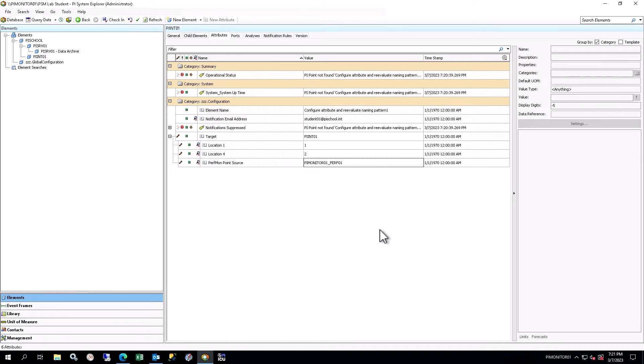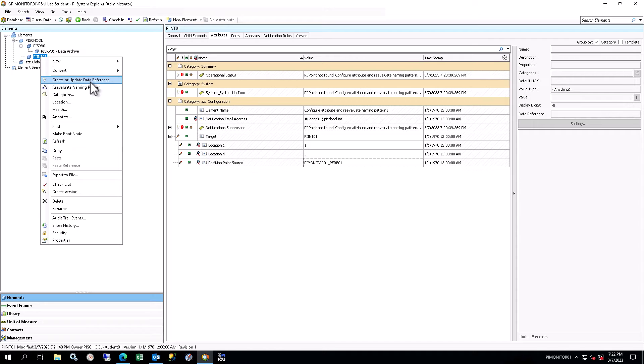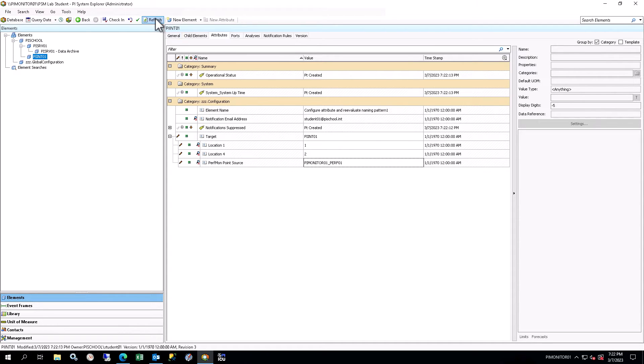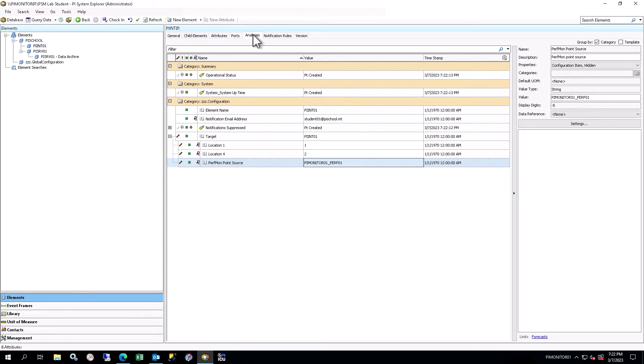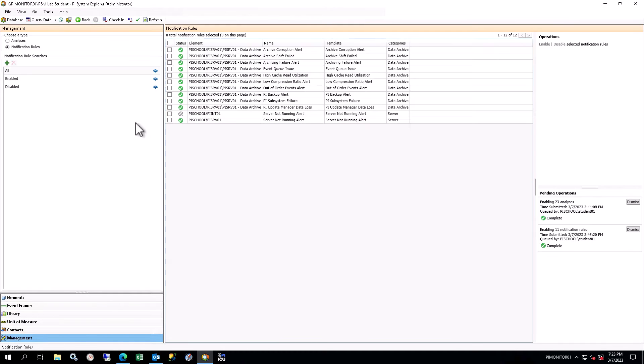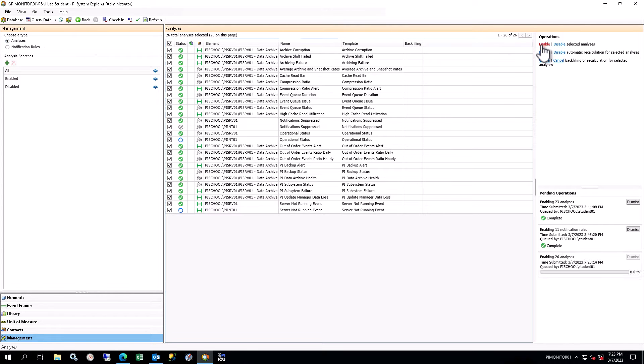There are additional attributes on the server template used to monitor the overall availability status of the server, and in certain cases, can be used to suppress notifications when a server or component is unavailable. To create the tags for PI Point data reference attributes, right-click on the PI INT 01 element in the browser and select Create or Update Data Reference. The Create Config window will show the progress of the creation. Once the tags have finished creating, select the Analyses tab in the viewer, and you will see a number of analyses defined for this element. As previously, the analyses are disabled. You can enable these analyses individually from here, or use the Management plugin from the Navigator to enable them all at once, and confirm that they have the correct status after startup.